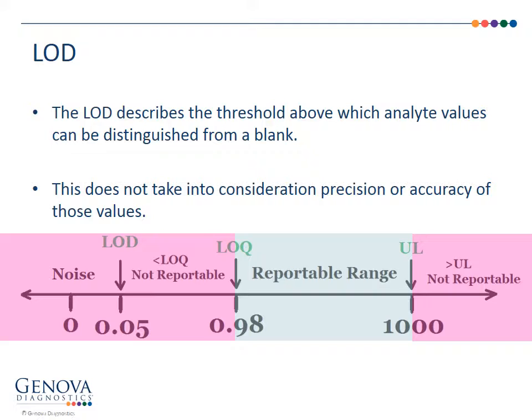But in some cases, our LOQs go pretty darn low, and the LOD and the LOQ start getting closer and closer together. The danger of that is, of course, if you start to have assay problems, or your instrument gets really dirty, or starts malfunctioning, or just ages, that LOD, the noise threshold, can start creeping up a little bit. So understanding where your LOD is in relation to your LOQ will help you with troubleshooting, and will help you understand when things are starting to age out.